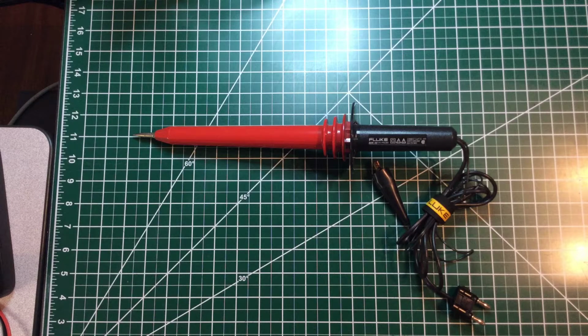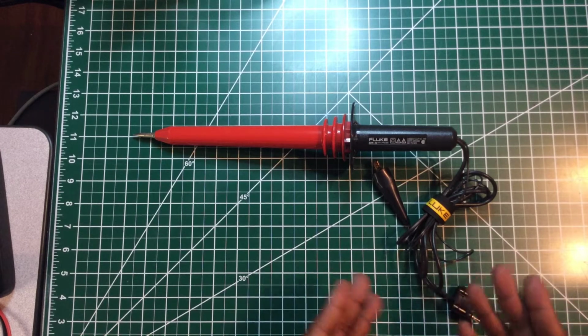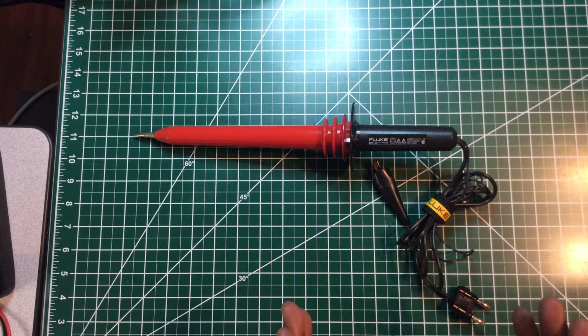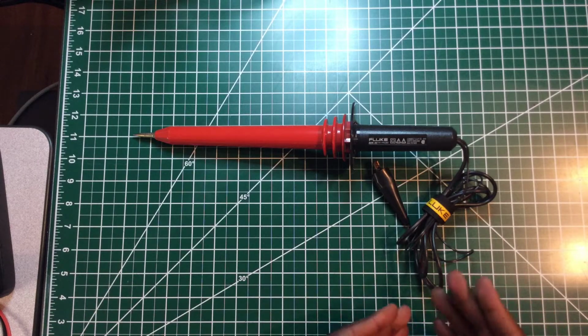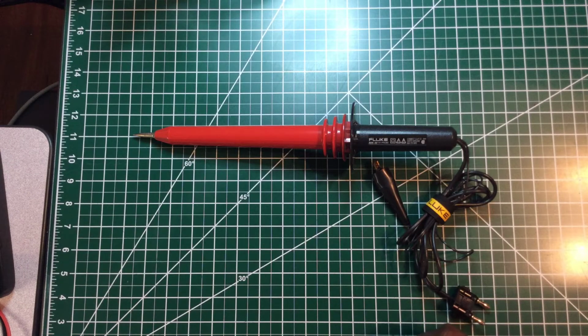So I'm going to read off the sheet of what this thing is capable of doing, the FLUKE specs. They say the model 80K-40 is a high voltage accessory probe designed to extend the voltage measuring capability of an AC/DC voltmeter up to 40,000 volts, over voltage category 1.